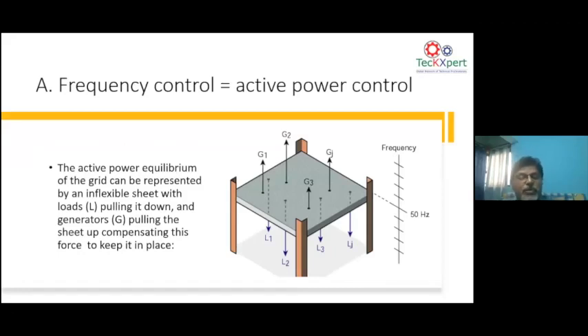Now, if you look at how the analogy of active power control works, as you can see, the network is compared to an inflexible sheet. This inflexible sheet, that is the network, is on one side pulled down by the load, and on the other side pulled up by the generator. So ultimately, you maintain the network at 50 hertz by balancing between the generation and the load.